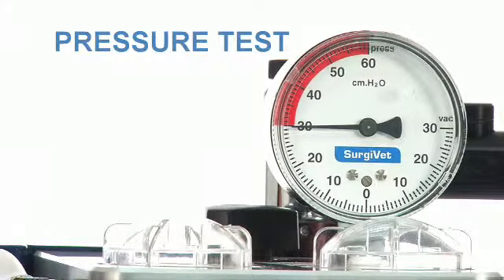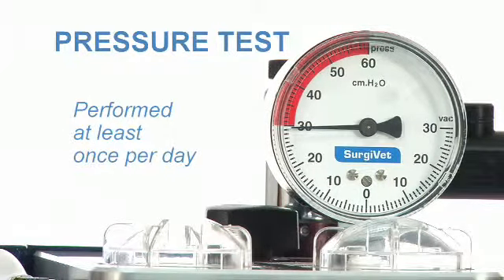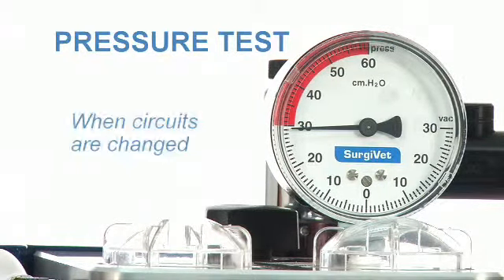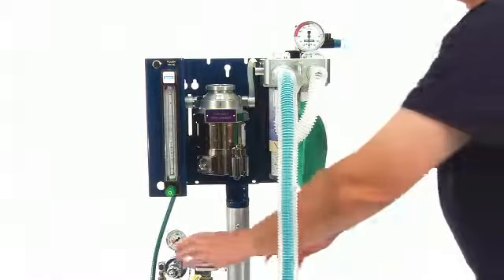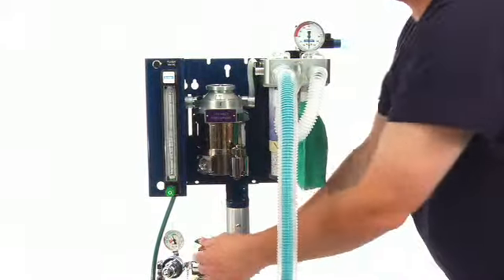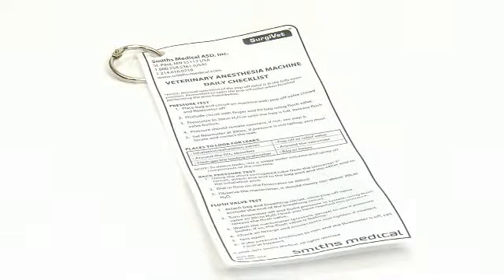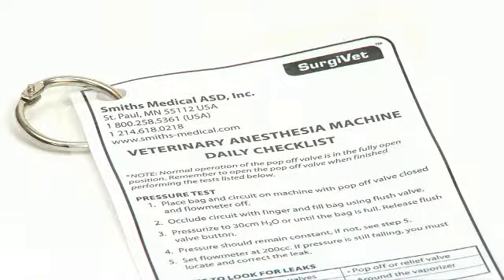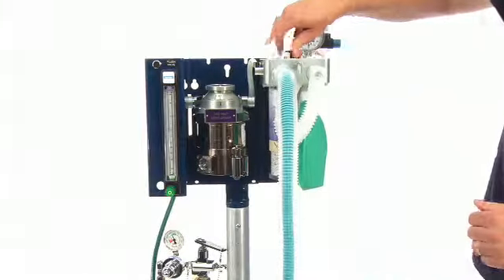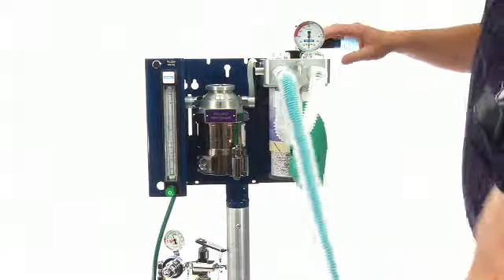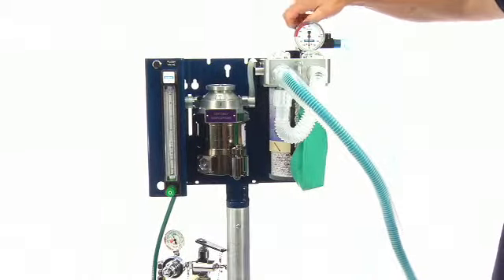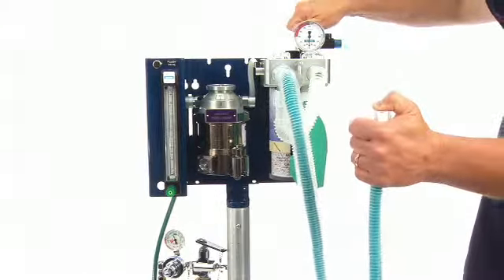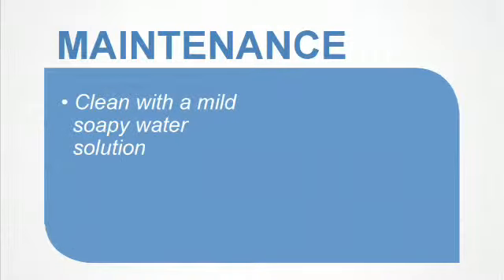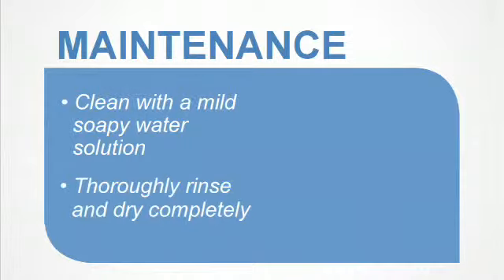A pressure test is recommended to be performed at least once a day, ideally before every procedure or when circuits are changed. Refer to the daily machine leak test portion of this video or the laminated card enclosed with your product on how to appropriately perform this on the SurgiVet anesthesia machines. Inspect the patient's circuits, hoses, and rebreathing bags daily or before each use for proper function and visual damage. These items can be cleaned with a mild soapy water solution. Be sure to thoroughly rinse and dry them completely.